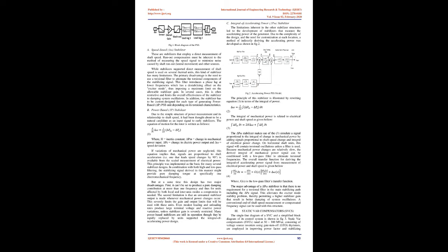the system. Under small disturbances, to remain in synchronization the machine requires positive damping, generally from a power system stabilizer, PSS, which is one of the most common controls used to damp out oscillations. The main role of PSS is to introduce a modulating signal acting through the excitation system for oscillation damping. It should be capable of providing stabilization signals over a broad range of operating conditions and disturbances. However, within nonlinear systems, the function of PSS is limited.